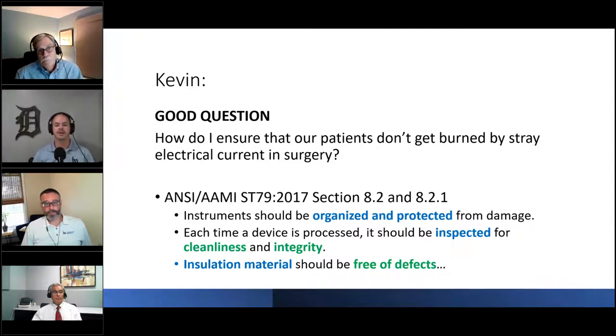It talks about inspection for cleanliness and integrity, and mentions insulation material being free of defects. Notice it didn't say anything about laparoscopic instruments only. Any insulated instrument applies here, or even better, any instrument intended to be used with electrical current.